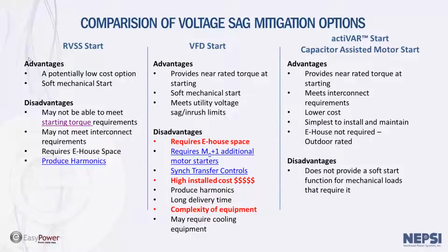In comparing these three technologies, we'll start with the reduced voltage soft start. The reduced voltage soft start has the advantage that it's a low-cost option. Typically, with a price tag of around $40,000 for a 5,000 horsepower motor, it is a low-cost option, and it's typically what is first looked at when considering the mitigation options. It also has the advantage that it provides a mechanical soft start to the load, because you can reduce voltage to the motor, reduce the torque, and therefore it starts the motor softly.